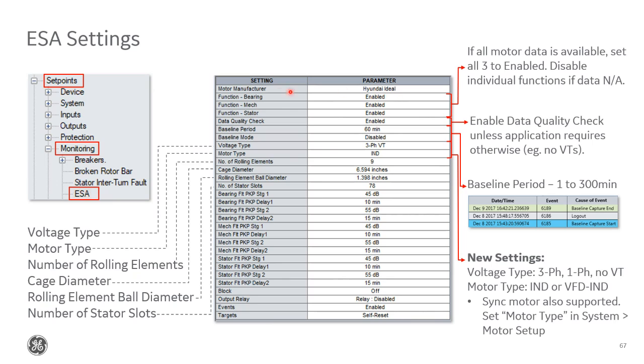The next three settings are the function. You can choose to enable or disable them. Generally, unless you have something particular, like you have bearing sleeves, for example, all of these would be enabled. If you have, let's say, sleeve bearings, you would disable this because we don't support sleeve bearings. The data quality check setting I mentioned earlier, generally you would leave this enabled unless you have a special circumstance that prevents you from doing so, like you have no VTs, for example. Otherwise, it's default to enabled.